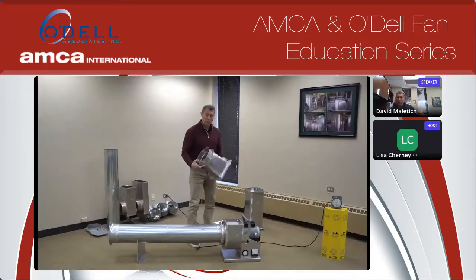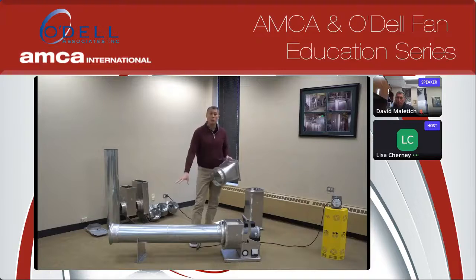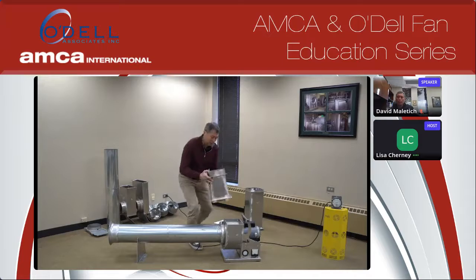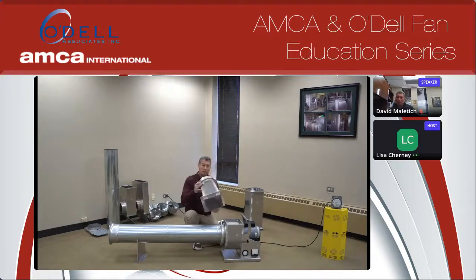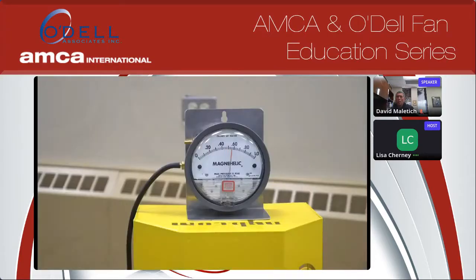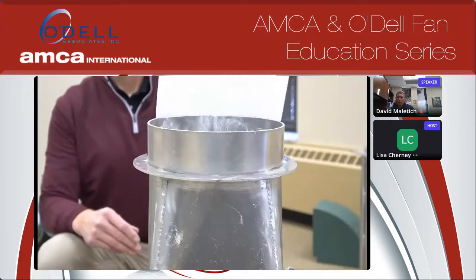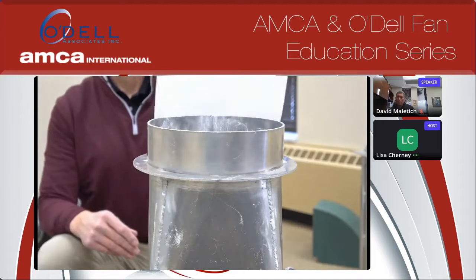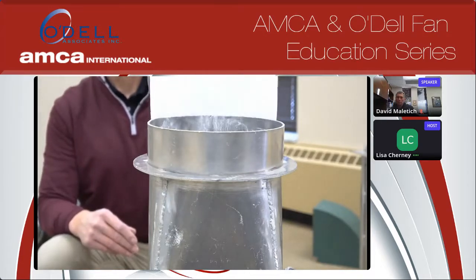So if we take this rectangular to round transition, the same one that we used when we were doing the inlet measurements, put it on the outlet of the fan, and again, no turning devices inside of it. Put it on the outlet. Notice that there is again an increase in performance when we look at the Magnehelic gauge. And if I take the same piece of paper, notice that even in this short distance here, we've already started to get some evening out of the velocity profile.